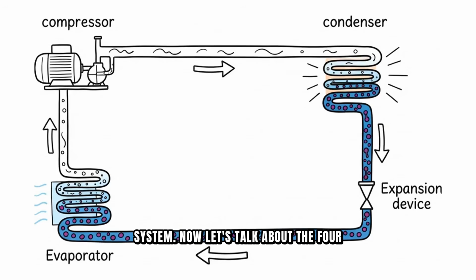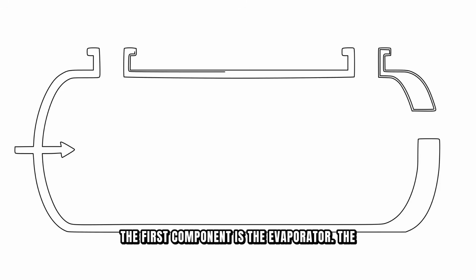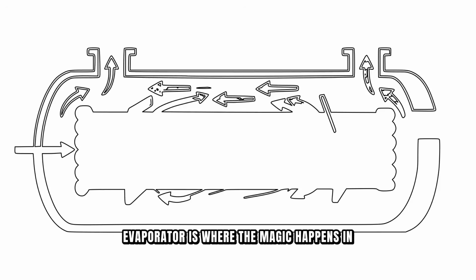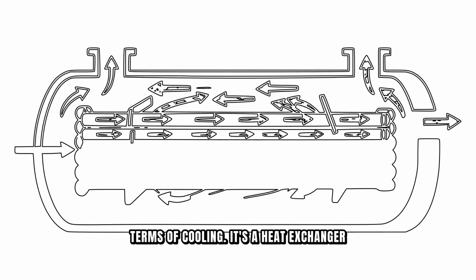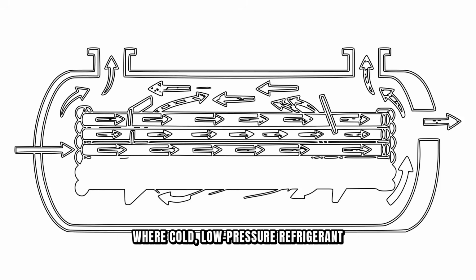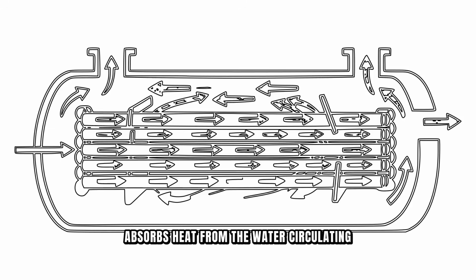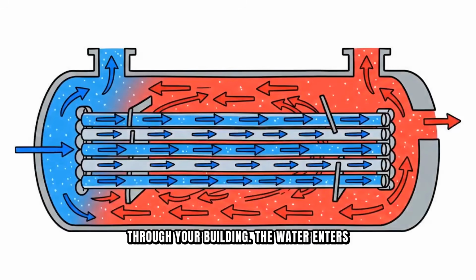Now let's talk about the four main components that make a chiller function. The first component is the evaporator. The evaporator is where the magic happens in terms of cooling. It's a heat exchanger where cold, low-pressure refrigerant absorbs heat from the water circulating through your building. The water enters warm and exits cold, ready to be distributed throughout the facility to cool air handlers and other equipment. The second component is the compressor.